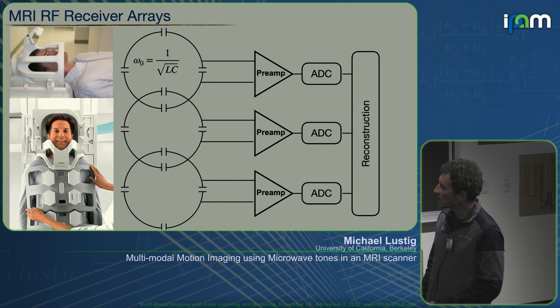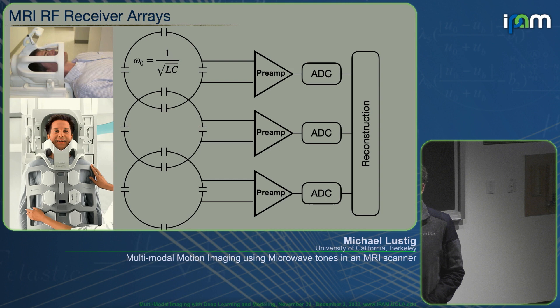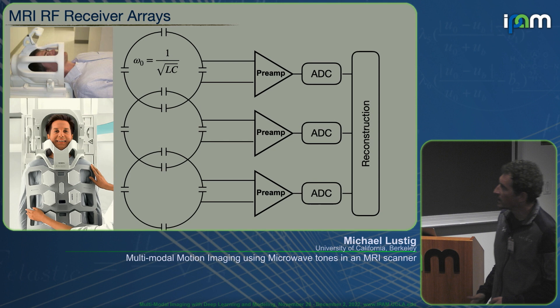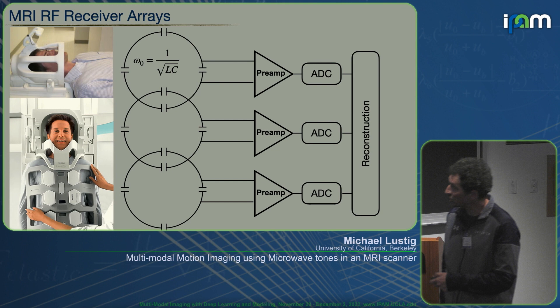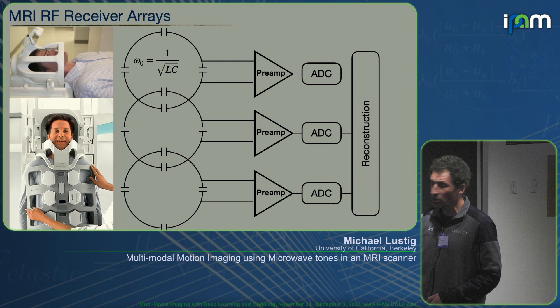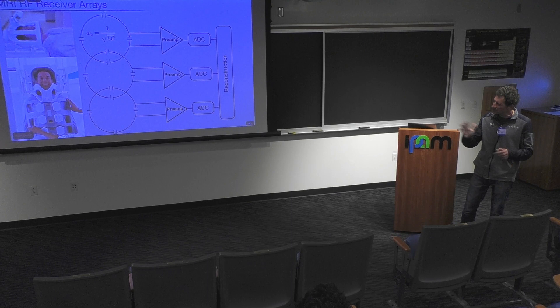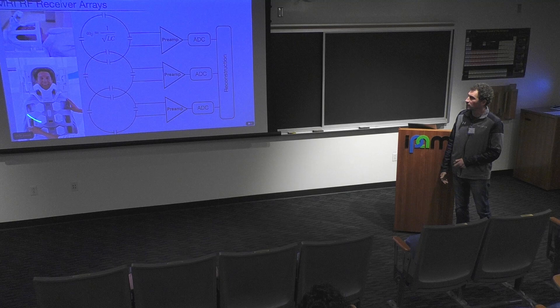The antenna that you put on the patient is really an array of receiver coils — loops that are each resonant to the particular frequency used for MRI. At 3 Tesla that's around 127 megahertz; at 1.5 Tesla it's 63 megahertz; at 7 Tesla it's about 300 megahertz. These are LC resonant circuits connected through transmission lines to preamplifiers. After preamplification, each channel is digitized and passed to reconstruction. Using these arrays allows parallel imaging and significantly increases signal-to-noise ratio since they are close to the body.